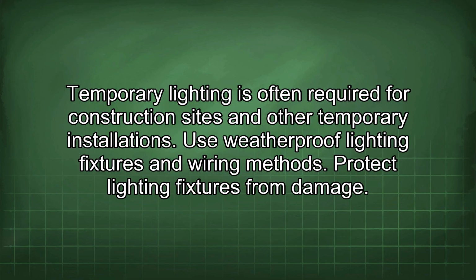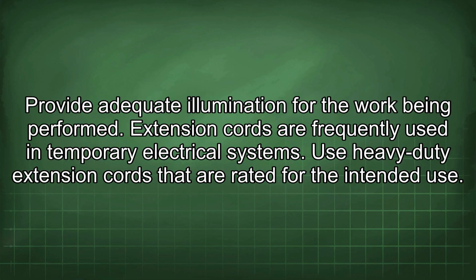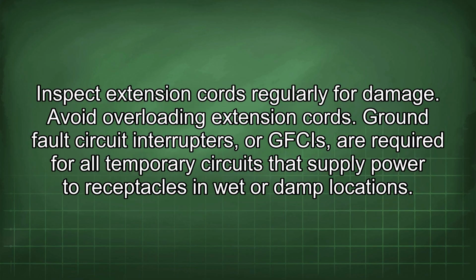Temporary lighting is often required for construction sites and other temporary installations. Use weatherproof lighting fixtures and wiring methods. Protect lighting fixtures from damage. Provide adequate illumination for the work being performed. Extension cords are frequently used in temporary electrical systems. Use heavy-duty extension cords that are rated for the intended use. Inspect extension cords regularly for damage. Avoid overloading extension cords.